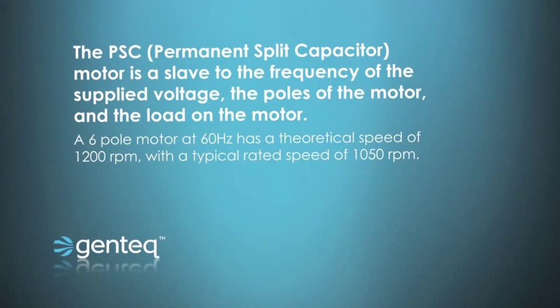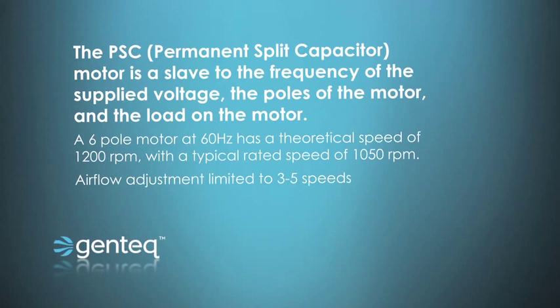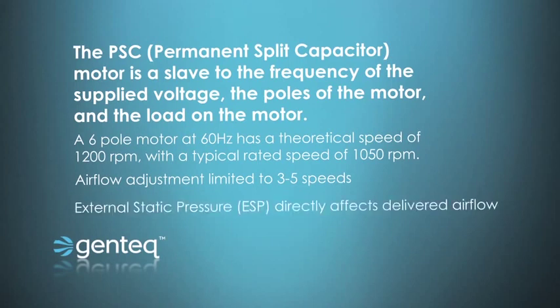To limit that even more, most PSC motors are three to five speeds, with five speeds being the max — most are only three speeds. So to get your constant fan, first stage heat, second stage heat, first stage cool, second stage cool — you don't have enough speeds to precisely deliver the exact amount of airflow for every demand like you do in variable speed. And finally, external static pressure: a PSC motor has no control over external static pressure. In fact, I like to say it's a slave to static pressure.